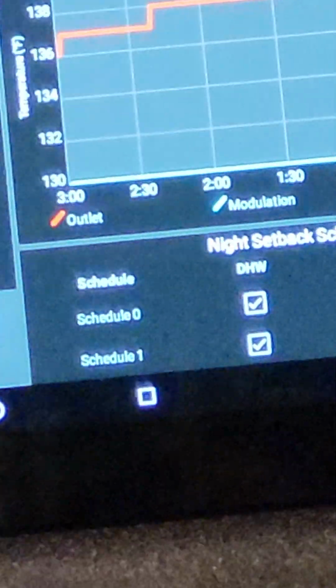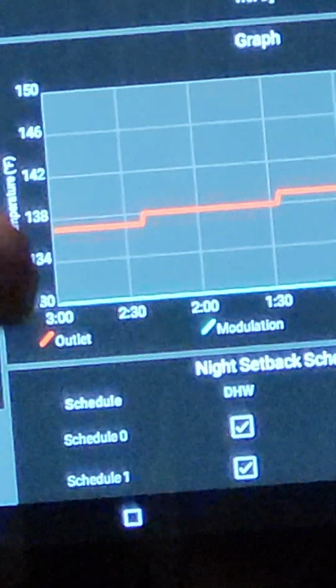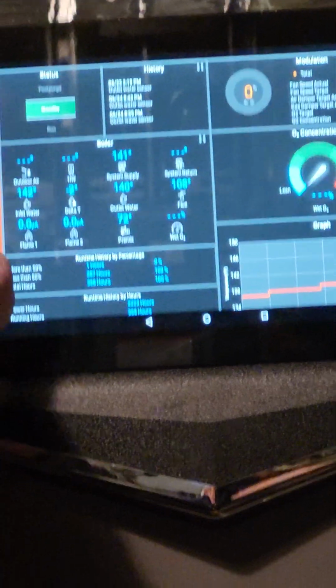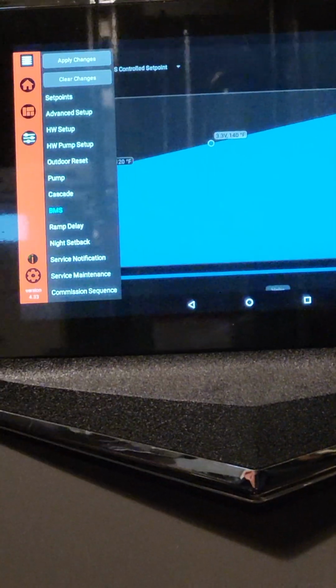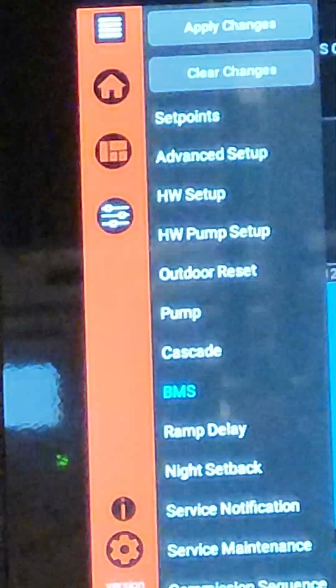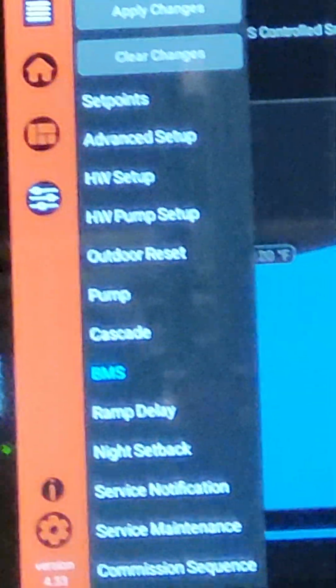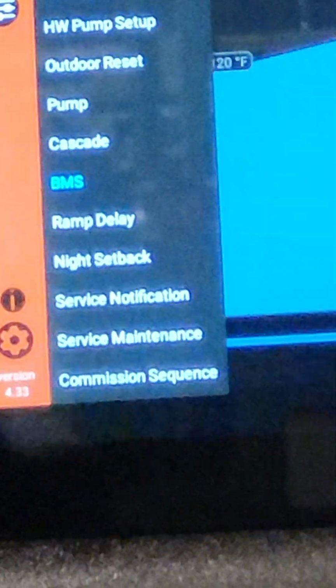Our runtime clock is here. If you were going to do night setback, that's there. That's disabled. No reason to do it when you're on BMS. And then the third button down is your installer menu. When you press that button, it's going to ask you for a password. The password of every Lochinvar Smart System boiler is 5309, just like the song, 867-5309. That's how you would get into this.